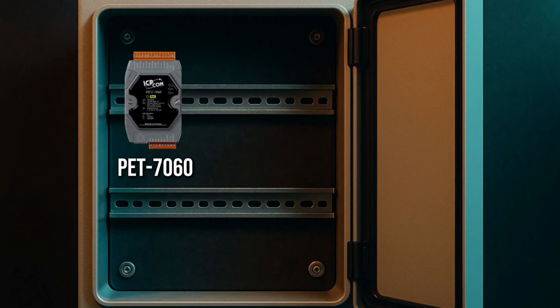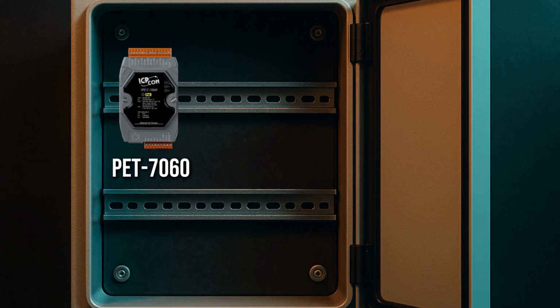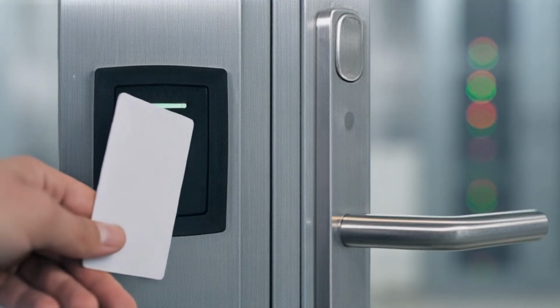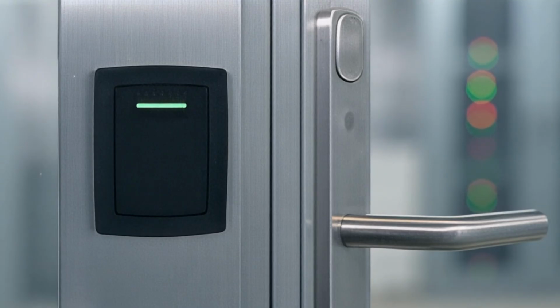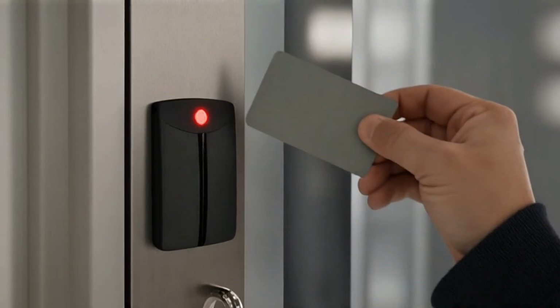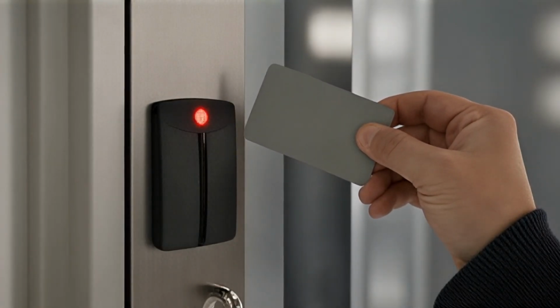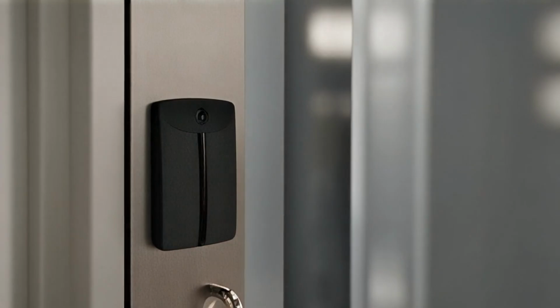So the goal became clear: centralize monitoring and control, reduce on-site patrols, and make the system smart enough to alert and act in real time. So here's how we made that happen. At each server room entrance, we deployed a PET7060 Ethernet I/O module. When one taps their card against the reader successfully, the PET7060 receives the query from the control center to open the gate. Conversely, when access is denied, the door remains closed and the data is sent back to the control center for activating alarm notifications. The system achieves access control effectively.